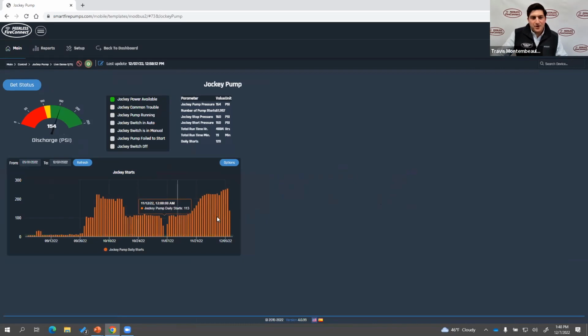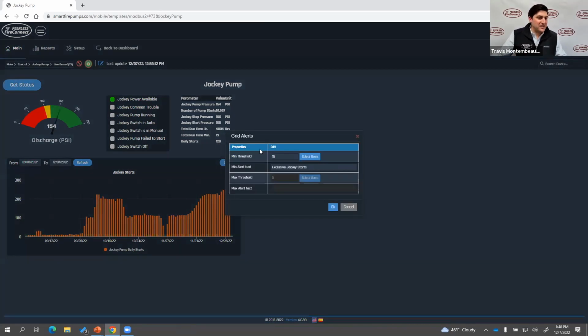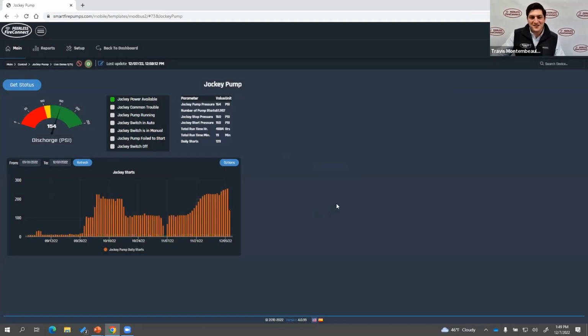We talk about jockey pump monitoring. One of the things is daily starts. So I can say, send me a text message if the last start was, say, 100 starts over here. Send me a text message if it goes to 120. So I change that to 120, select the users, and anytime it jumps up, we'd be getting a text. And in this case, we'd probably be getting a good amount of texts here.